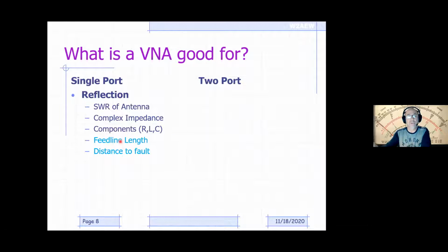By measuring essentially the frequency response and then looking at where you get some peaks and nulls due to that discontinuity in the feed line, you can use that to compute what the length is, or even a distance to fault. I mean, let's say you've got an antenna up on a tower and all of a sudden things aren't working so well. You can run this distance to fault test to see if you've got a break or a short or an open or something like that in your feed line partway up the tower without having to go climb the tower. Of course, you'll have to go up to fix it, but at least you'll know how high you have to climb.